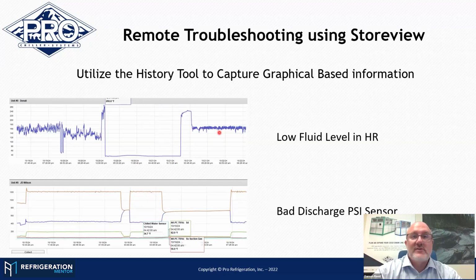And the technician's first reaction is, well, we've got bad electronic expansion valves. Well, why would you say that? Well, the suction pressure is way low and it should be coming up, but it's not. And so then you start peeling the onion, and you want to peel the onion from the outside in. You don't want to try to get into the core and dig it out. So outside in would have said, do you have enough glycol in the reservoir? I don't know, we didn't check that. That didn't come up in conversation until step 10. Well, steps 1 through 9, we just made sure everything was good, but it's a time factor. You're just wasting time if you don't start at the basics and then work your way in. Most of the time, it's one of the basic items.